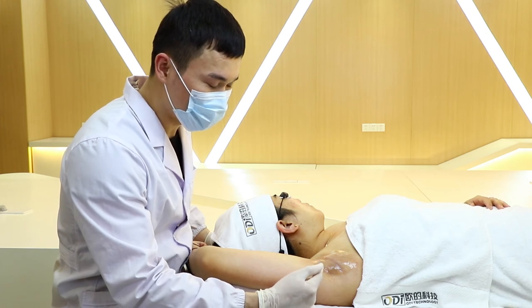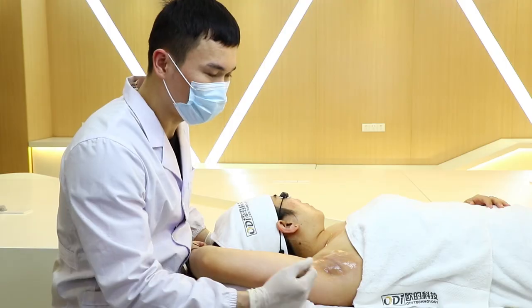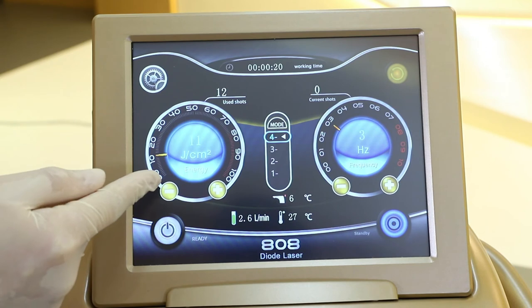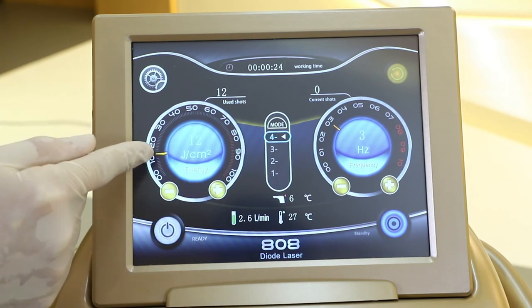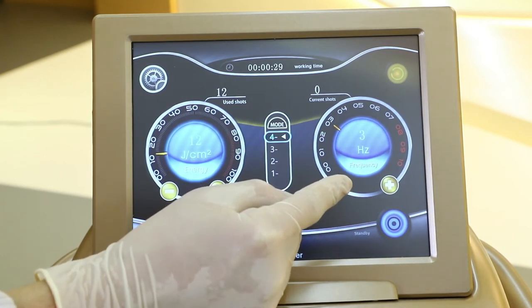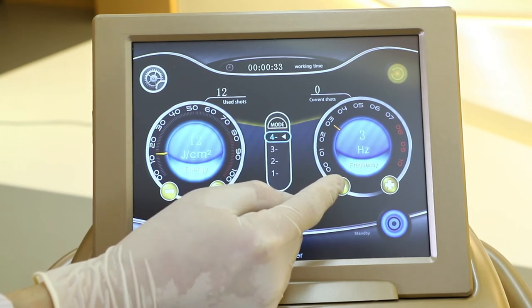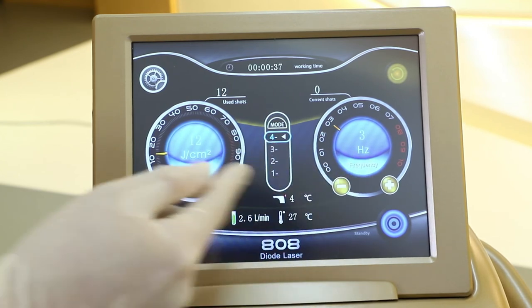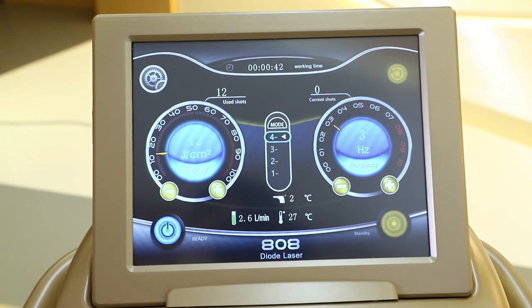So the energy we can start from 12 to 20 joules, and we should start from the lower end — beginning at 12. For the frequency, we should choose 2 to 4. Because the armpit area is not too big or too small, we can choose 3. After setting the parameters, we can set the machine in ready mode to start the treatment.